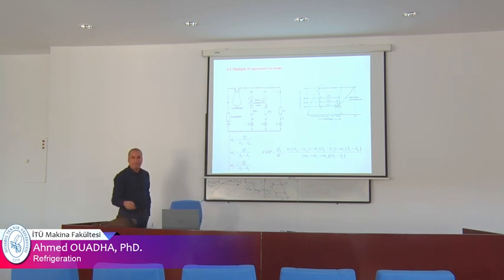refrigerator. So for example, here I give an example of a one-stage refrigeration cycle composed of a compressor, three evaporators, a condenser, three valves, and back pressure valves. The compressor will deliver vapor to the condenser. It condenses, then the condenser delivers refrigerant to the three valves. This is valve one, valve three, valve two, and the other valve.